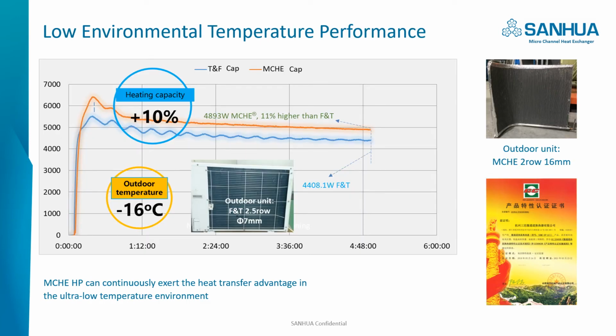For a heat pump, when the environmental temperature gets down, it's getting difficult to match the heating capacity and the heating load. But luckily, when the environmental temperature gets down, the absolute humidity is also getting quite low, and you will not see frosting and defrosting on the heat exchanger so frequently. So we did the comparison testing of microchannel and the fin tube heat exchanger at the -16 ultra low temperature environment that is typical for Northern Europe and Northern China.